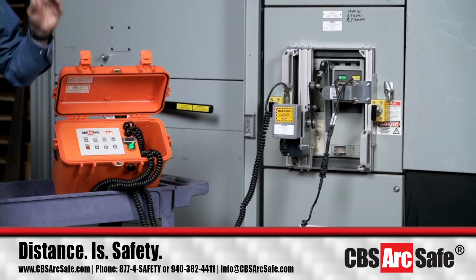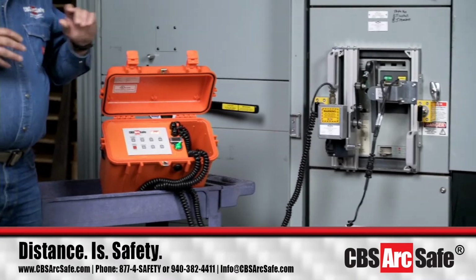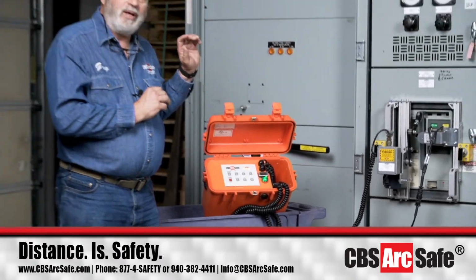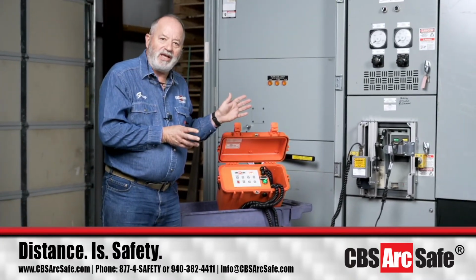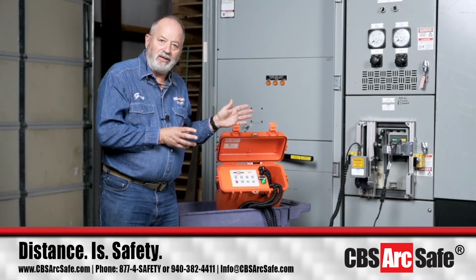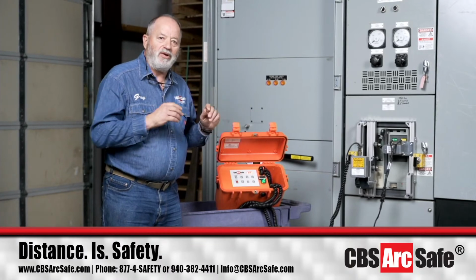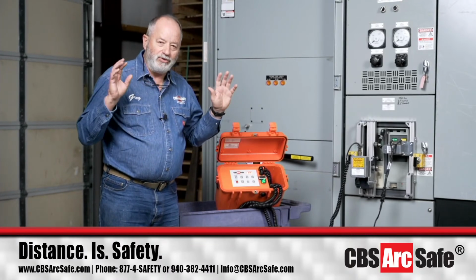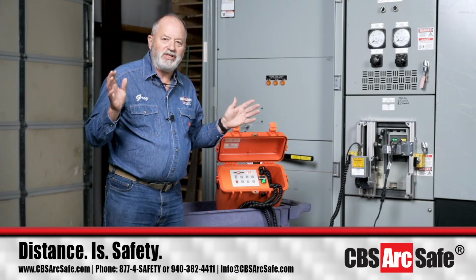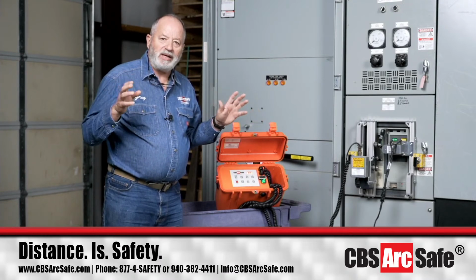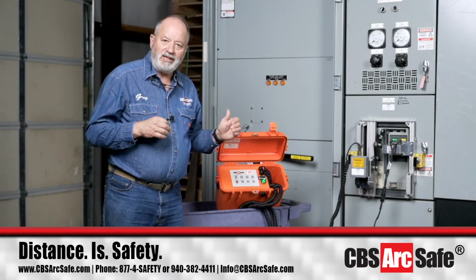Remember, we're doing this for a demonstration right now, but always read your arc flash labels and walk that distance off to operate this gear. While you see me standing here, if you're dealing with dead switchgear and doing a demonstration, that's fine, but always respect that arc flash hazard boundary and get that distance.